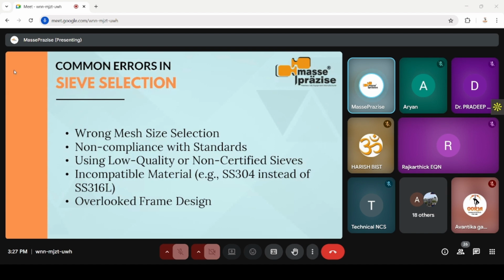First one is wrong mesh size selection. Choosing a mesh size that is too fine or too coarse. Suppose you have a requirement of 710 and you have wrongly selected 650 or 800. That may lead to undesired fine or oversized particles. Choosing mesh sizes that are too fine or too coarse for the intended particle size distribution can lead to oversized or undersized particles passing through, that can affect the blend uniformity, flow properties, and tablet compression.